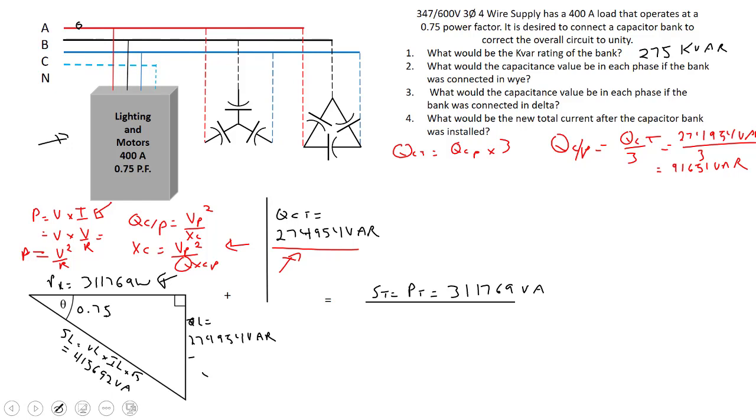We are ready now to use this equation and our VARs per phase to figure out what it would be in Y and delta. Let's go in Y. XC is going to equal our phase voltage squared divided by our VARs per phase from our capacitor bank. In this case our phase voltage in Y is root 3 less than 600. I'll use 346.4 volts for more accurate results.